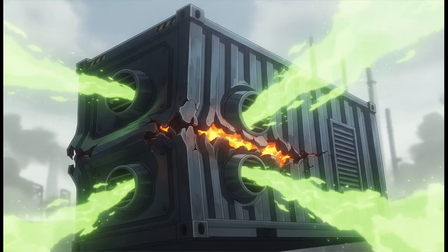Once thermal runaway starts, the system faces hazardous off-gassing and the potential for a catastrophic explosion if not managed perfectly. The extreme heat breaks down the electrolyte molecules, generating highly toxic hydrogen fluoride gas. So it's not just a fire hazard anymore, it's a severe chemical and explosion threat.